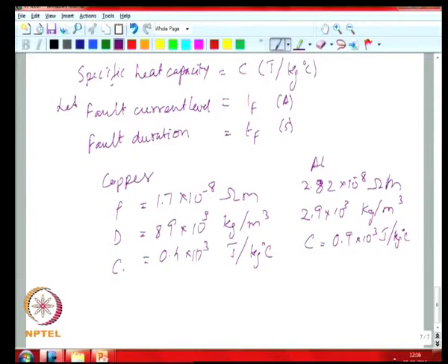So, you could get a feel for what would be the resulting properties if you have these different types of conductors. So, we will look at an example to look at a piece of say 12 gauge wire and see what it takes to protect it. Okay. If you look at the ampacity of the wire, it is roughly 25 amps if you look at the wire tables. So, you should be able to carry that level of current.